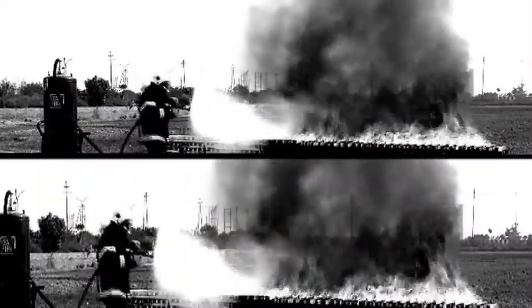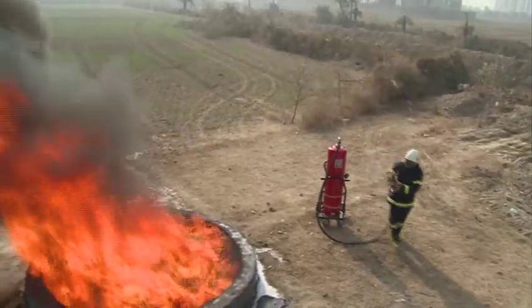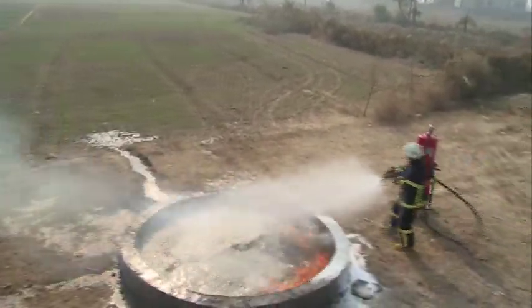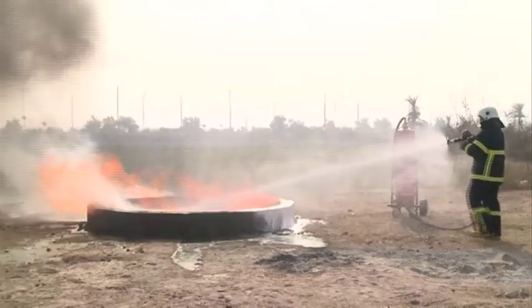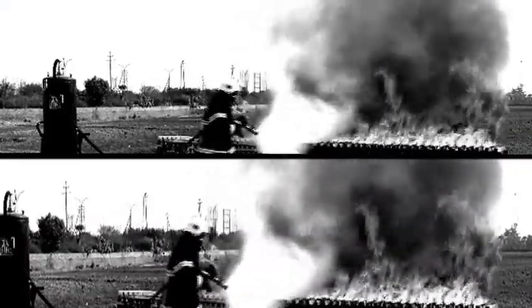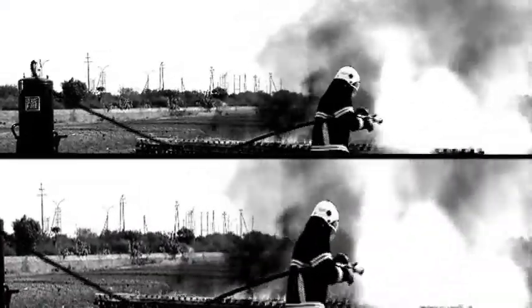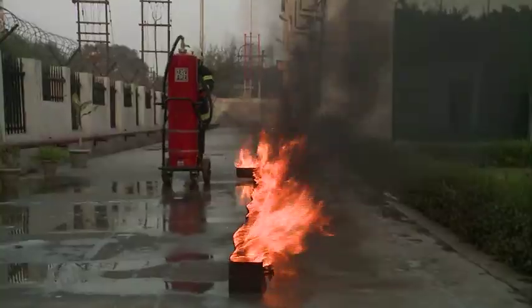This is how the Quad takes on a real-life fire. It harnesses water's immense cooling powers and multiplies them hundreds of times over. The Quad's water mist technology breaks water down into a fine mist of under 80 microns. This mist is then thrown at the fire at great kinetic force, covering a large surface area. As soon as the mist comes into contact with the fire, it instantly turns into steam, enveloping the flames, cutting down the oxygen supply and reducing temperature to below combustion levels.